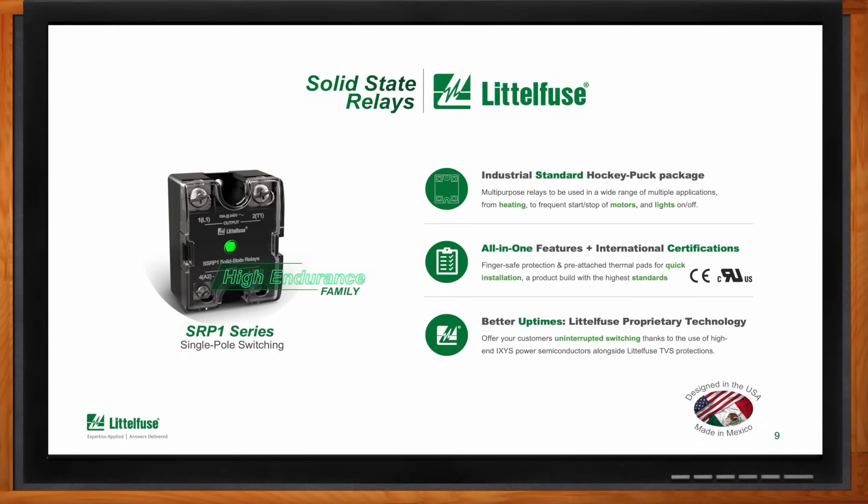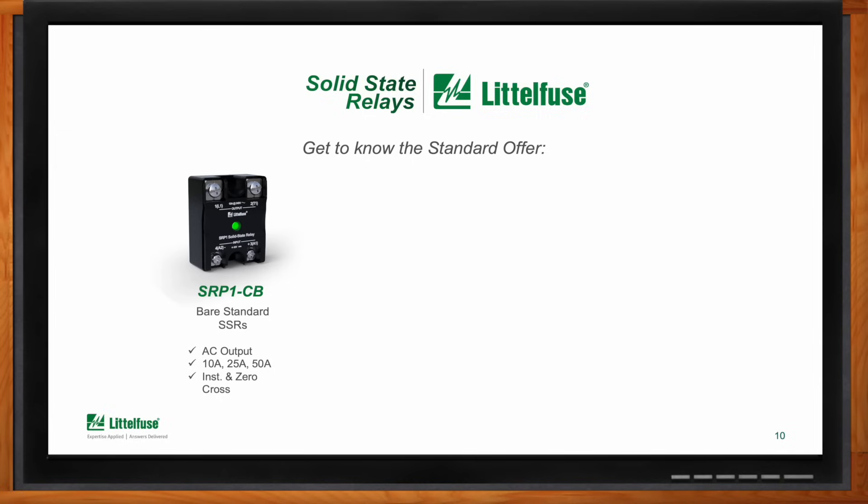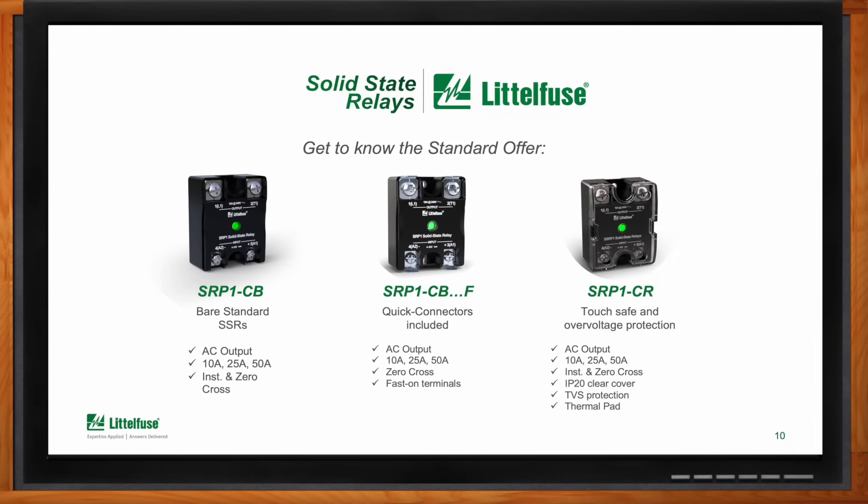There are three versions in this series. The CB version is the classic bare standard option for those needing flexibility. The CBF version comes with fast-on terminals, mostly used in food and beverage equipment. The CR version is the all-in-one product featuring finger-safe protection cover, over-voltage protection on the output, and an integrated thermal pad for quick and easy installation. All versions control AC loads up to 50 amps and up to 600 volts, with instantaneous and zero-cross switching options to control different load types.